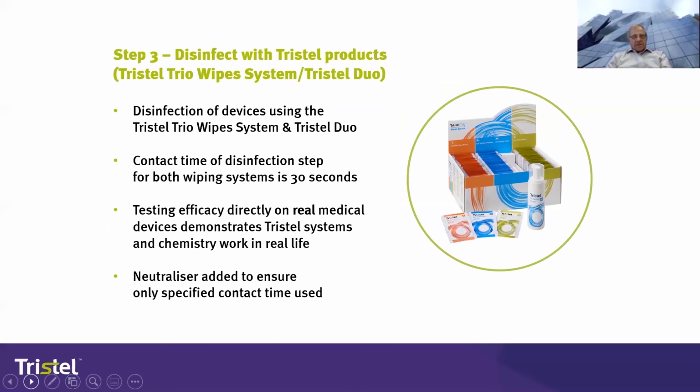The devices, once they have the virus and the soil dried on them, are disinfected according to the user instructions. The contact time for disinfection is 30 seconds. Once the contact time was completed, the devices were neutralized to stop any residual chemistry from having microbial effects.